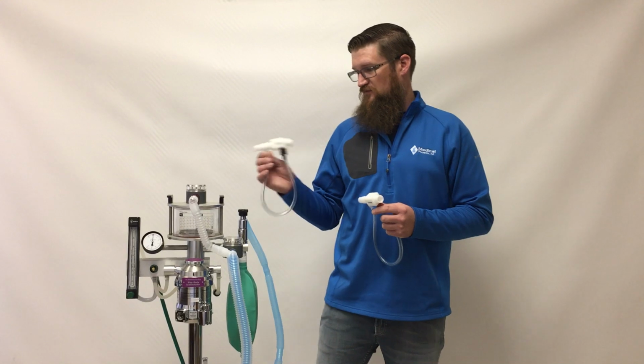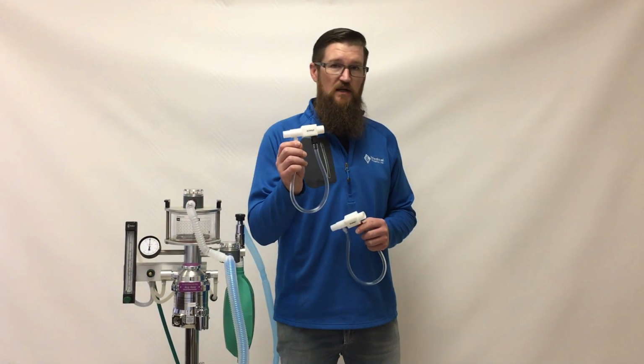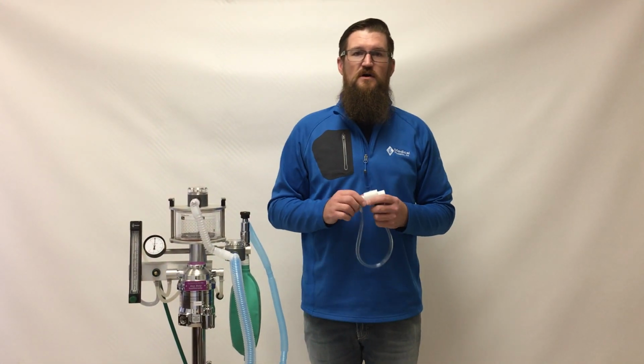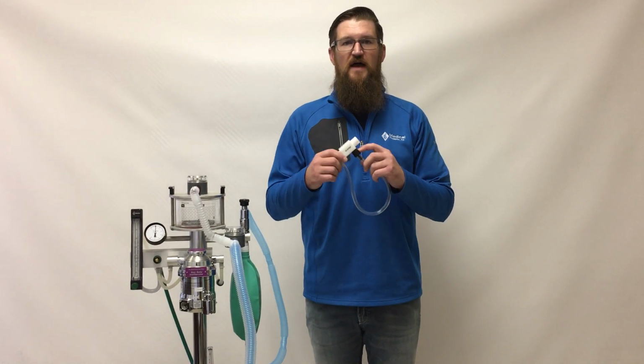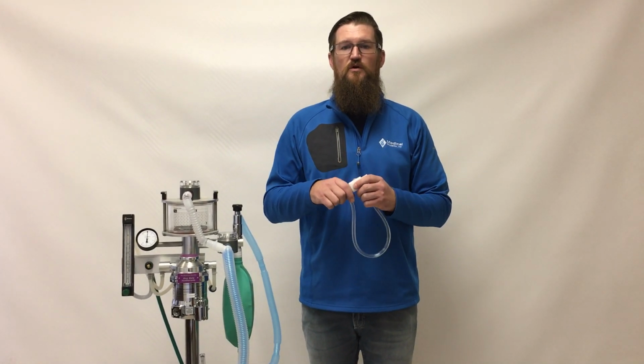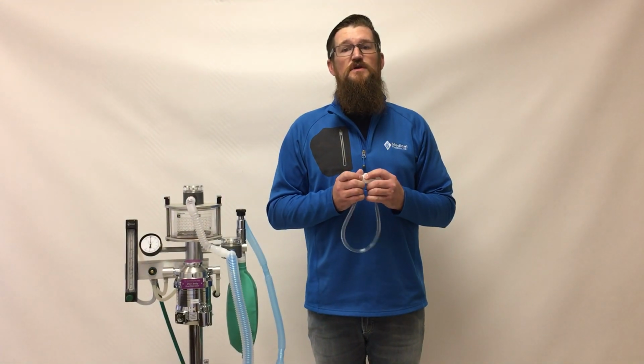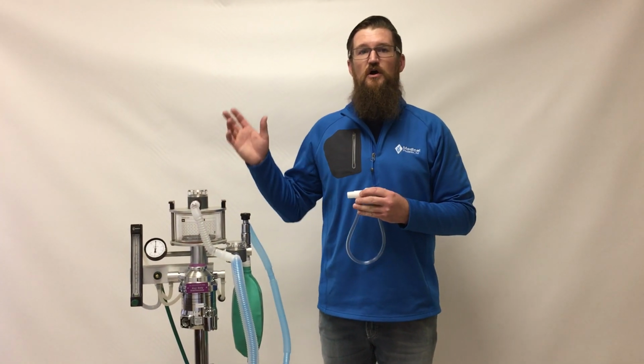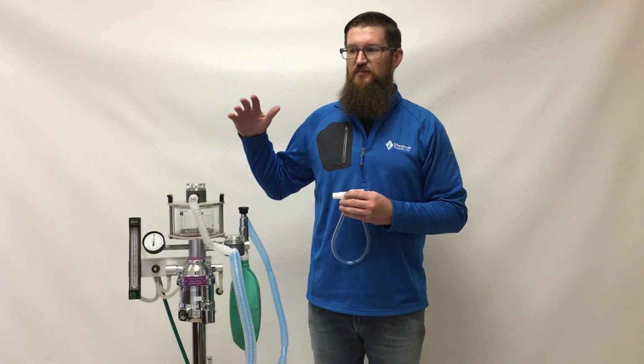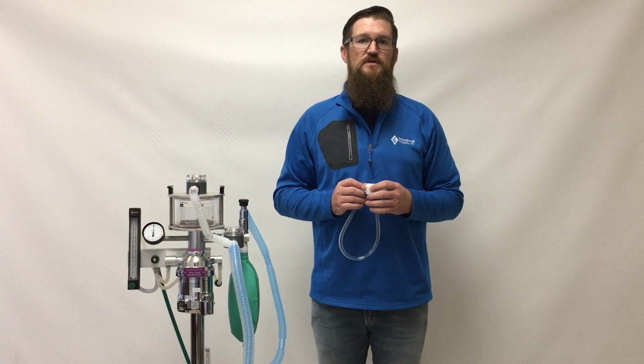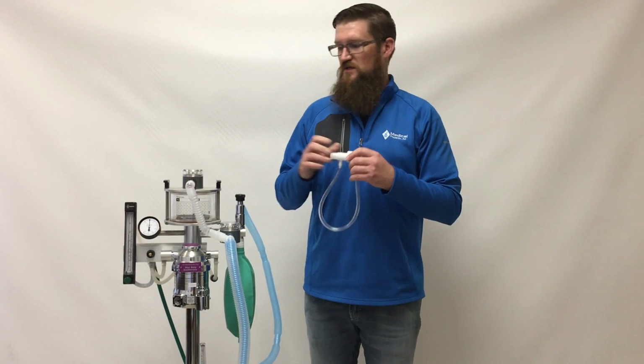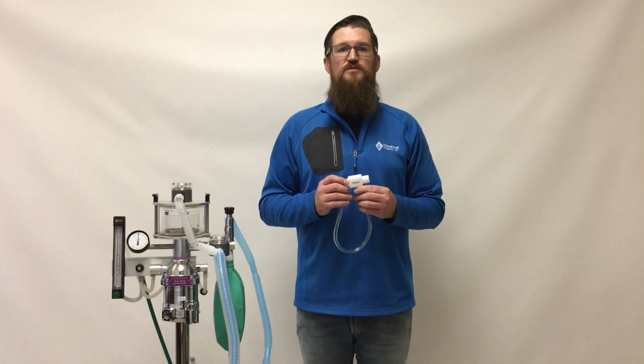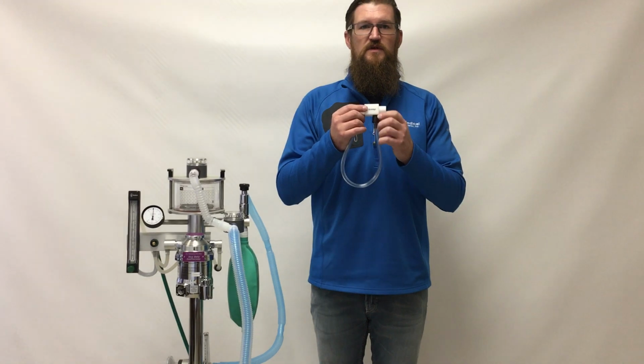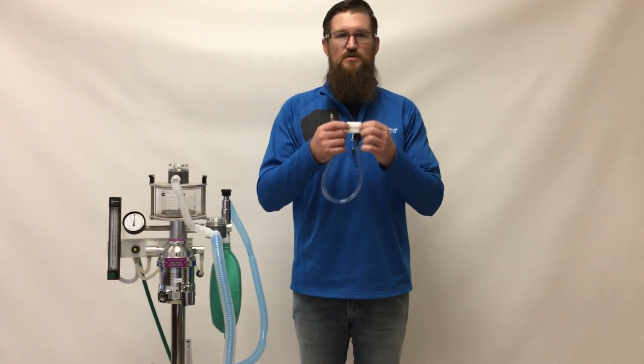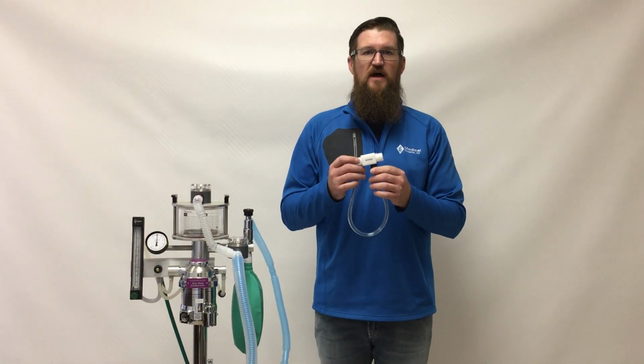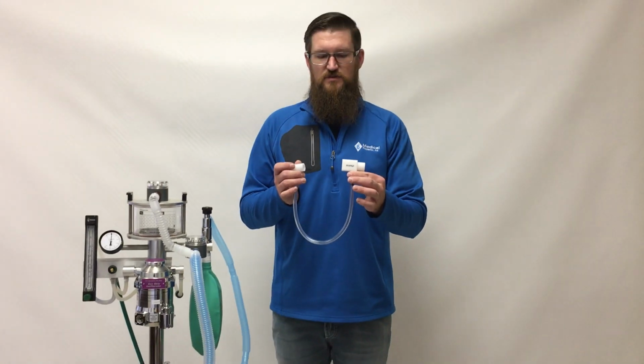So today we are going to, especially for demonstration purposes, focus on the JDM-SAFETY20. But the SAFETY30 is an optional product noted by the red valve and the inscription on the side that says 30 centimeters of water pressure. For reference, this has come up a couple times. Centimeters of water pressure is the common unit of measure for patient circuit pressure. Since PSI is probably the most common pressure unit that anybody is used to, but since the circuit pressure does not build up to the PSI range, centimeters of water pressure is used. So as indicated on the side, the valve will go up to and start blowing off at the inscription. This one is also denoted by the black valve, the JDM-SAFETY20, which will blow off at 20 centimeters of circuit pressure.